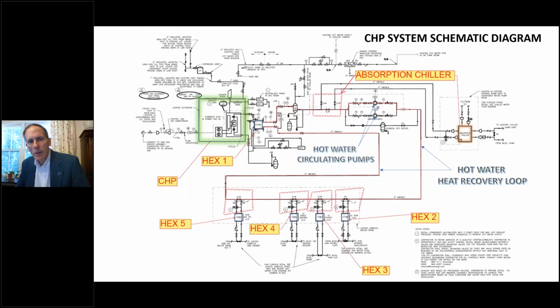Inside the building, hot water is circulated to various heat-utilizing components, including absorption chillers shown in pink on the right-hand side. The routing of the hot water heat recovery loop is shown in red line going through the building, and also provides heat to a series of heat exchangers located at HEX2, 3, 4, and 5 at the bottom of the drawing.